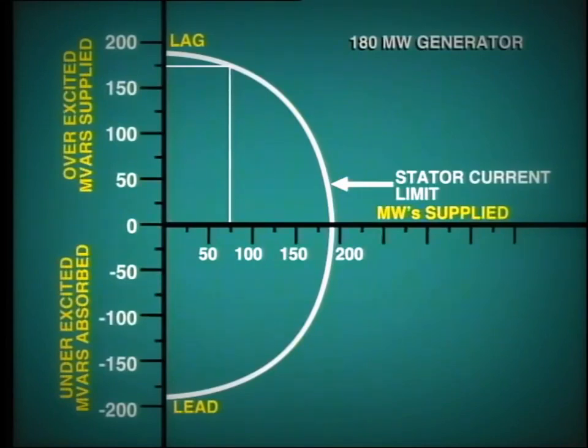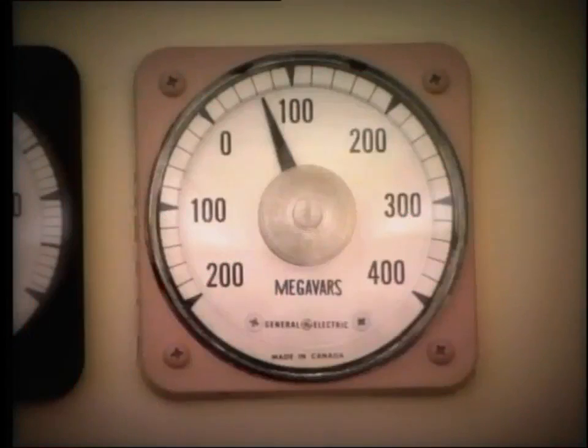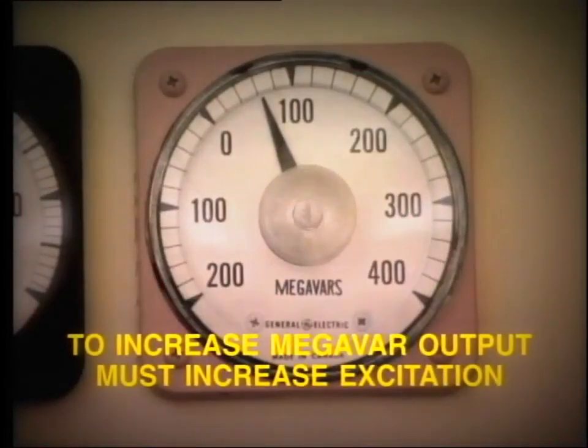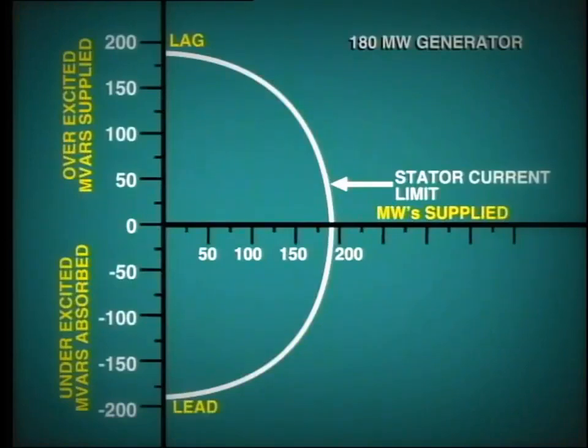However, there are other limits to observe in generator operation. As we know, in order to increase the megavar output of the generator, we must increase excitation. The increase in excitation current flow increases the heating of the rotor winding.